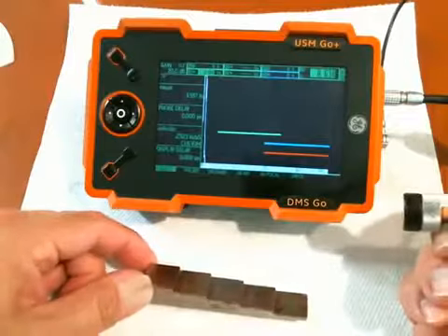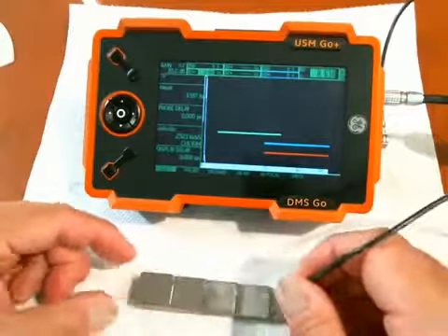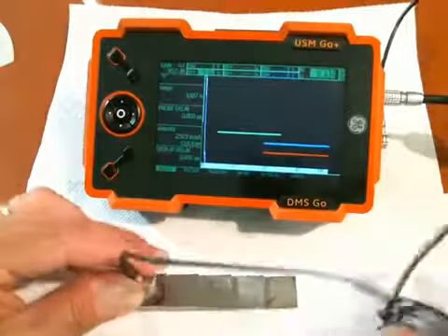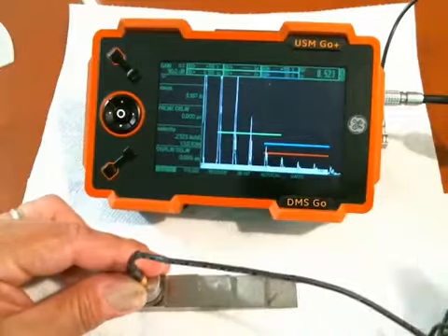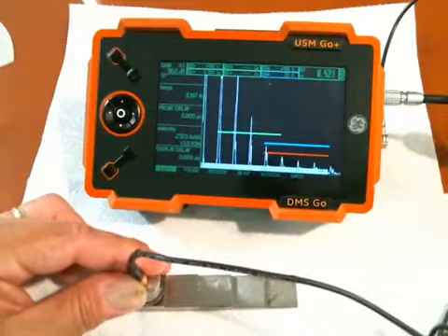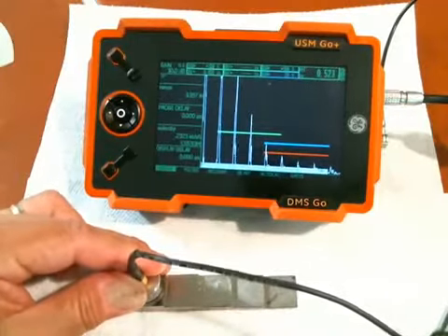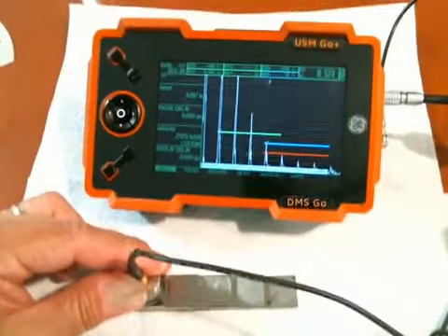So I have a CA211 here, a simple single element probe. I have a 5-step block with steps from 0.1 inch to 0.5 inch. Okay. If I put my probe on the 0.5 inch, we see my reading is 0.523. Okay. So I know that block is actually a 1/2 inch, so why is that wrong?